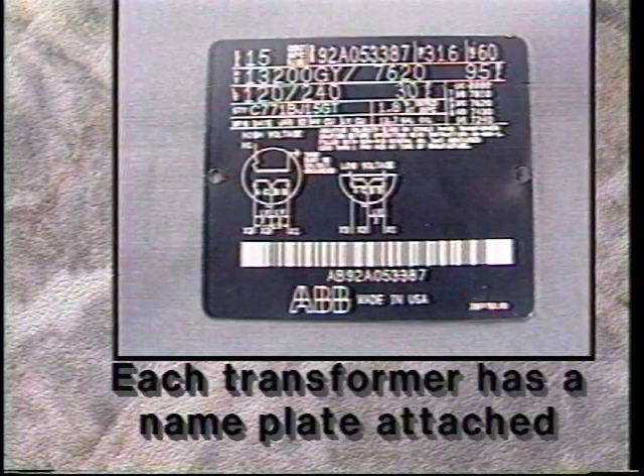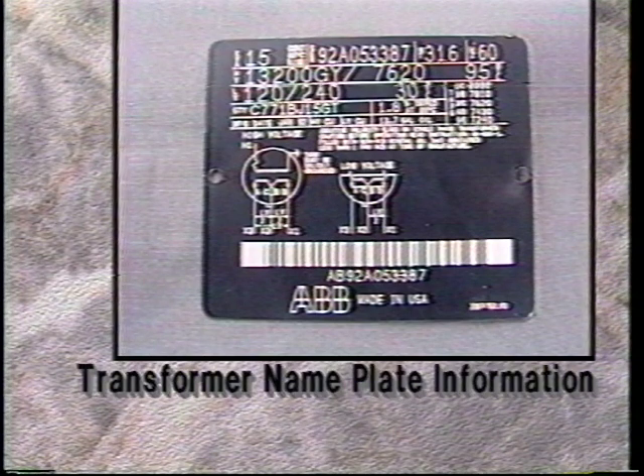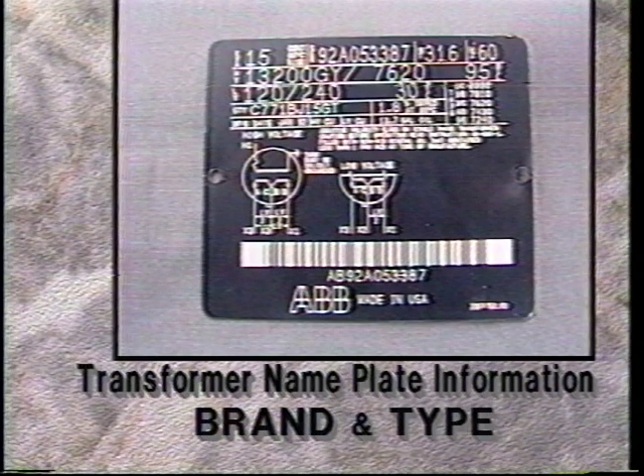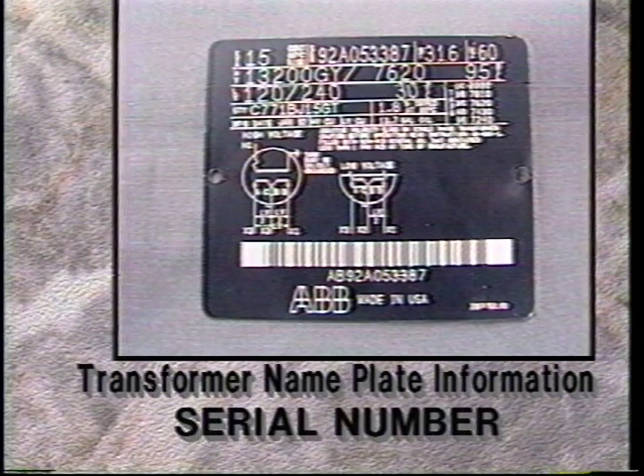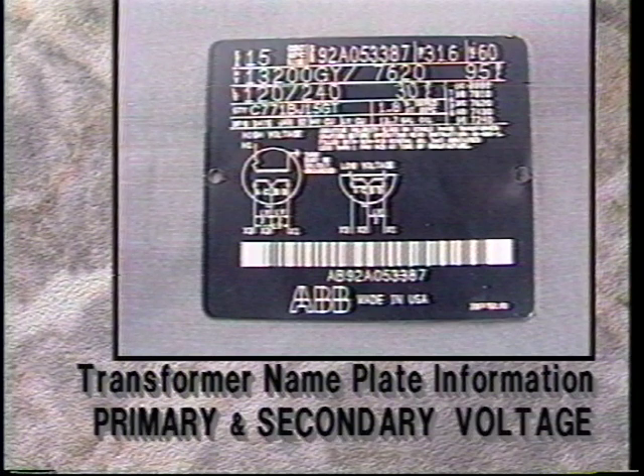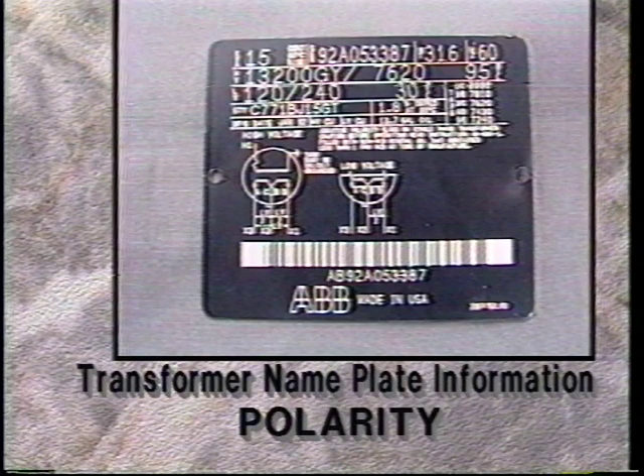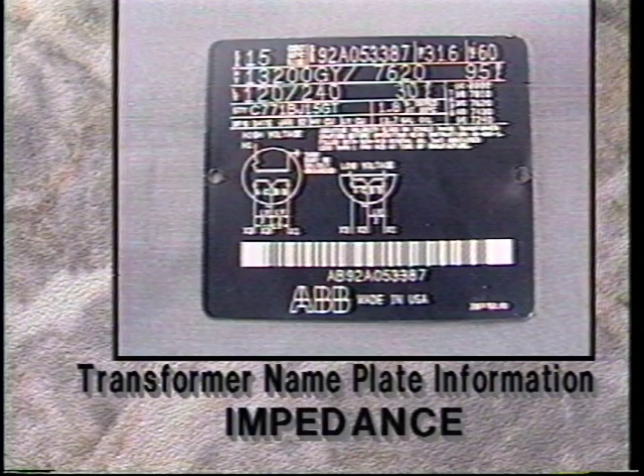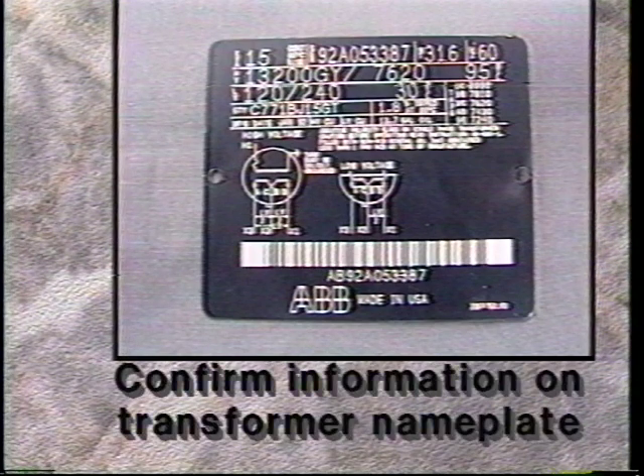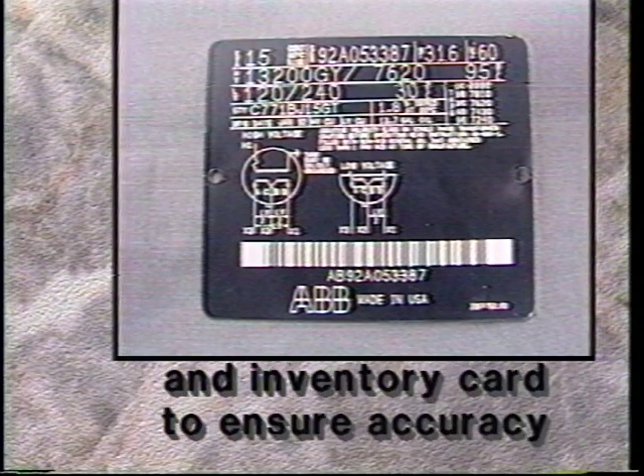Each transformer has a nameplate attached. This plate contains important and useful information for linemen. The information normally contained on a nameplate is brand and type, number of phases, a serial number, primary and secondary voltage, polarity, kVA, impedance, and taps. Confirm the information on the transformer nameplate and associated inventory card to ensure its accuracy. The transformer utilized in this video is a CSP type, which signifies the transformer possesses automatic self-protection.